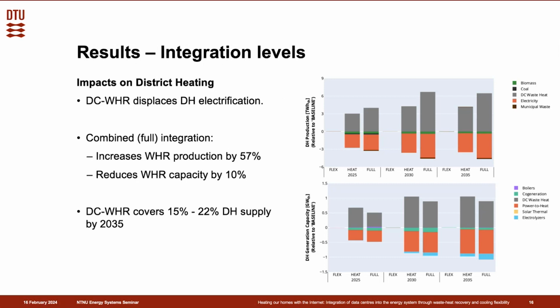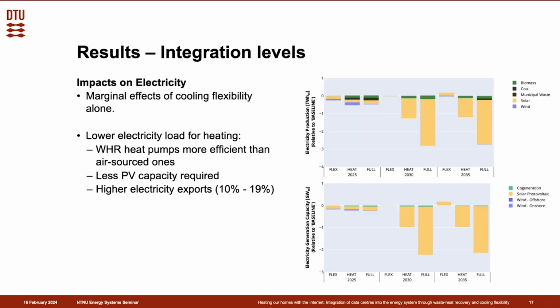More importantly, we see that if we combine the flexibility integration and the waste heat recovery, we can actually recover 57% more heat and reduce the capacity of heat installations as well, which translates into cost savings. All in all, data centre waste heat recovery can cover between 15 and 22% of the national district heating supply by 2035. On the electricity side, first, we see marginal effects of cooling flexibility.